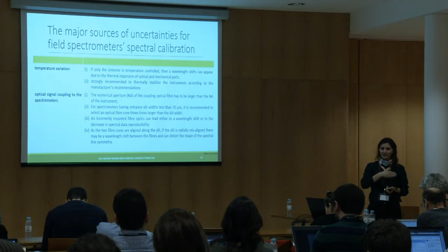I don't know if you need a characterization of this kind of lamp because it contains gas. Gas molecules have specific absorption lines, so the position related to the wavelength value for those peaks is very clear. The only change can be due to the aging of the lamp, so the intensity of the peaks. And the values of each peak, you can find in the NIST database, I think.